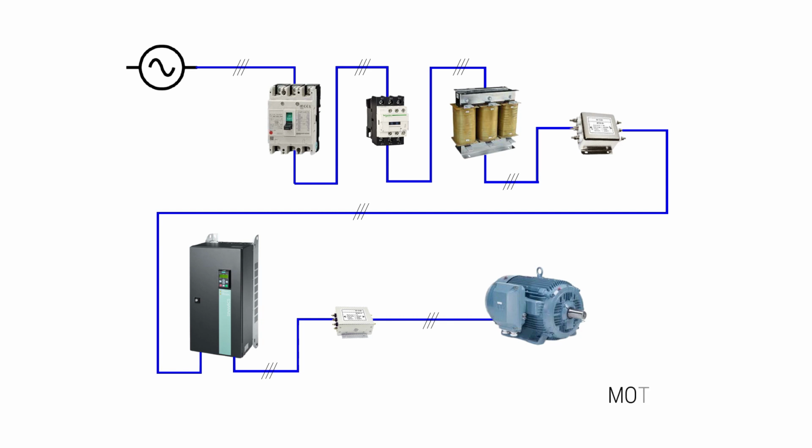Motor. When multiple motors are driven in parallel with a VFD, the VFD rated current should be at least 1.1 times the total motor rated current. Make sure that the motor and the variable frequency drives are separately grounded.